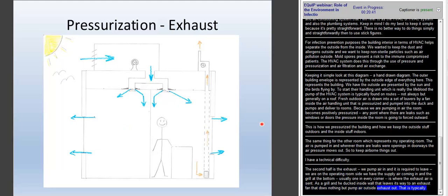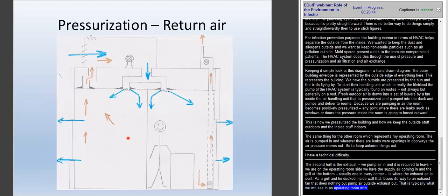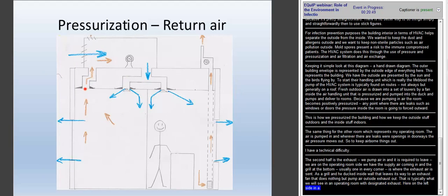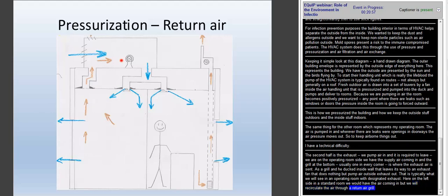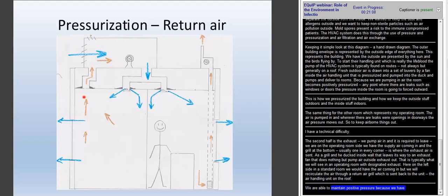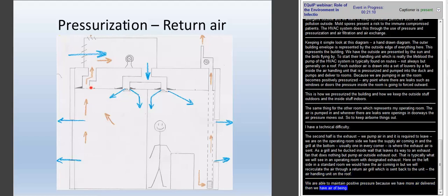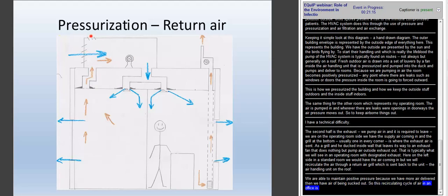But over here on the left side, in a more standard room, we would have the air coming in, but we will recirculate some of that air through a return air grill, which is also ducted back up to the air handling unit up on the roof. So we're able to maintain positive pressure because we have more air being delivered than we have air being sucked out. This recirculating cycle of air in an office is rather typical. A portion of this air is mixed with the fresh outdoor air that's coming in, and a smaller portion is exhausted out the top.